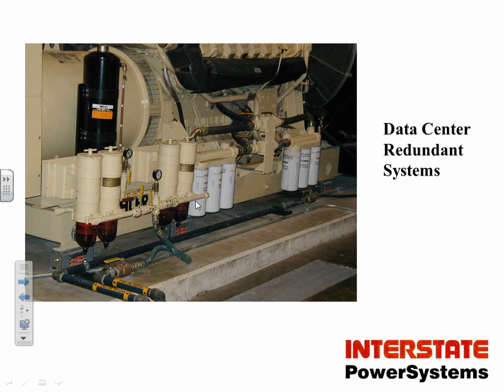There's actually 2 sets of oil filters on the thing. So if this system had to run for any duration of time, you could actually change oil while the thing was running by switching filters. So it's a pretty sophisticated system. No, 1 oil reservoir, but 2 sets of filters that are switchable here. You can see them in the picture. Same thing on the fuel. 2 sets of fuel filters as well.